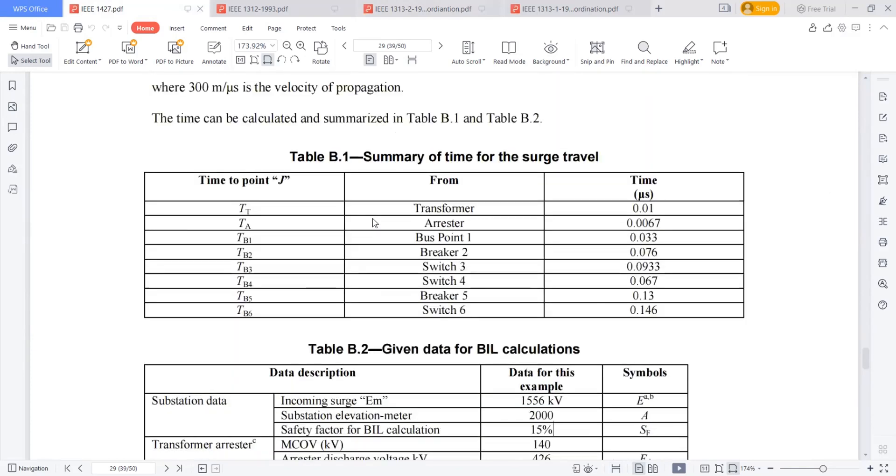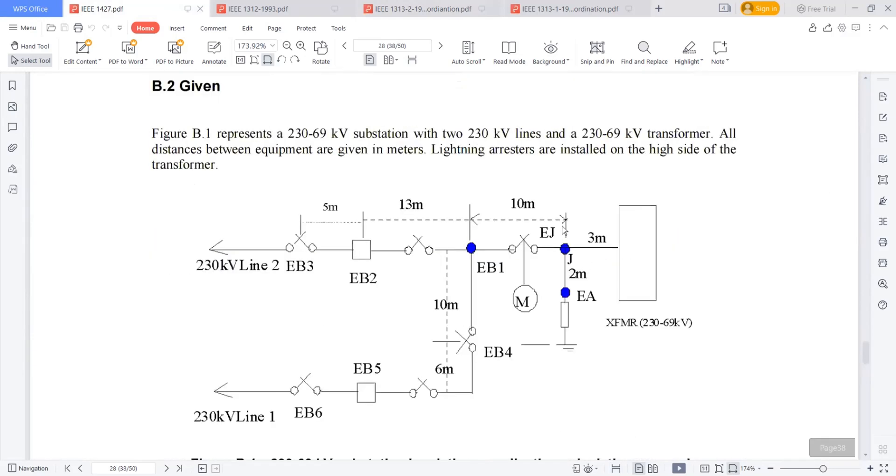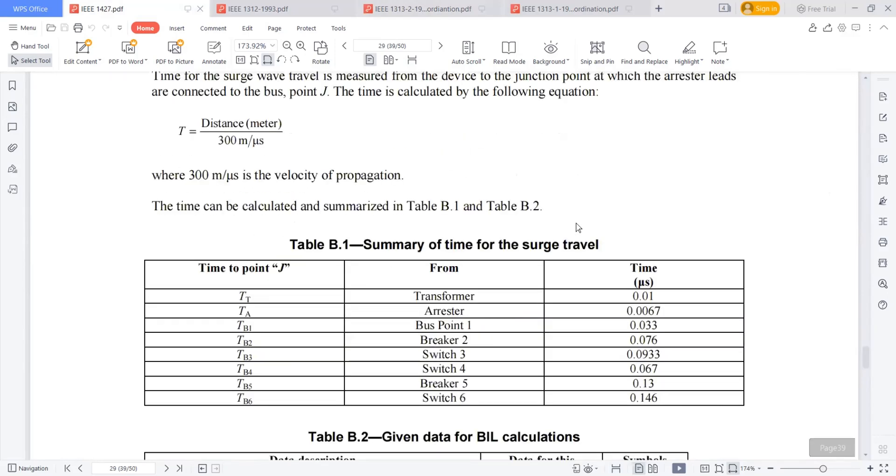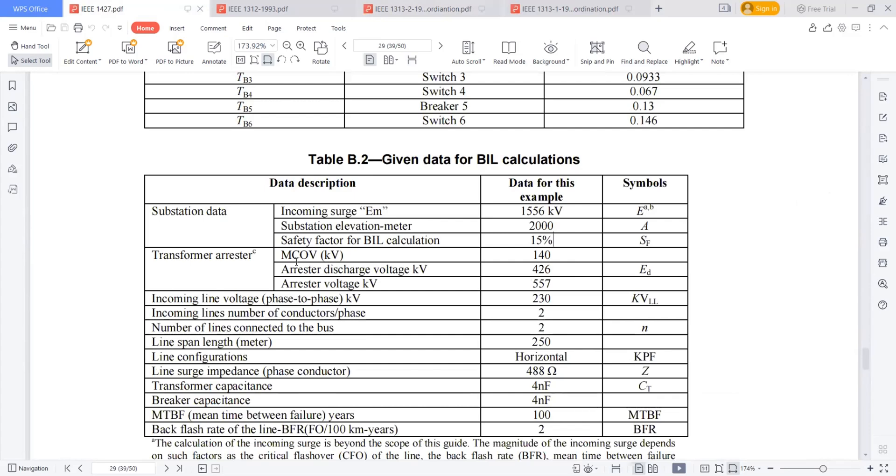The safety factor for BIL calculation generally we will consider 15% as a safety margin. The transformer arrestor, I am talking about the arrestor, which is a very important equipment playing a role here in this exercise. The transformer arrestor, the maximum continuous operating voltage of the arrestor, I considered 140 kV.